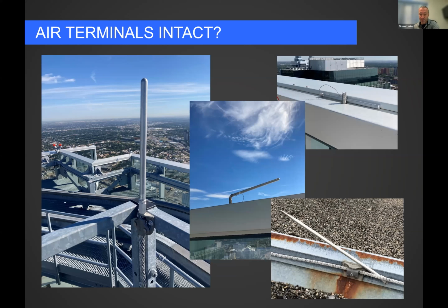Although if you look closely at that, you'll find one of the common failure points on a lightning protection system. That base is cast aluminum, with a little stub that sticks up and the lightning rod screws down on top of it. You can see an intact assembly on the left-hand side there, same kind of stub, same kind of adapter. The air terminal screws into that, but that is a common failure point - it snaps at the base, and the stub is now stuck up inside the adapter at the base of the air terminal.